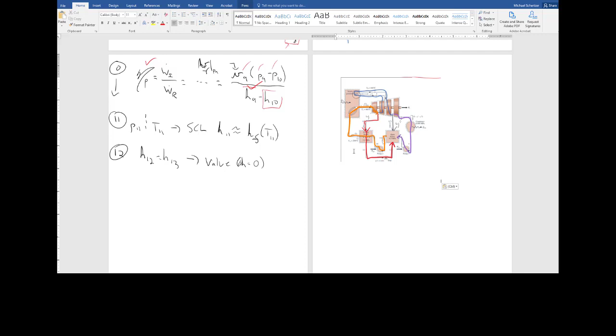So as we move through here, if I use this as my control volume, it's going to be just the same equation that we got there. So the CV is the now closed feed water heater. This is going to be steady state, adiabatic, passive. It's not one inlet, one outlet, but we're going to say that the change in kinetic energy is approximately equal to 0, which is equal to the change in the potential energy. And what that's going to tell us is that 0 is equal to the sum of m dot in, h in, minus the sum of m dot out, h out. This is a common equation for heat exchangers when we know information on both sides and we're not solving for Q dot.